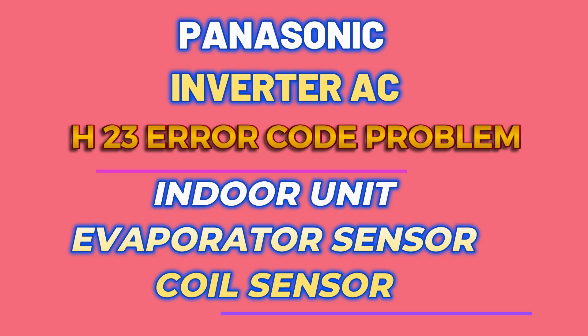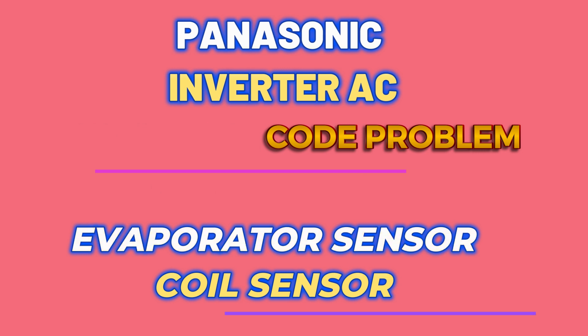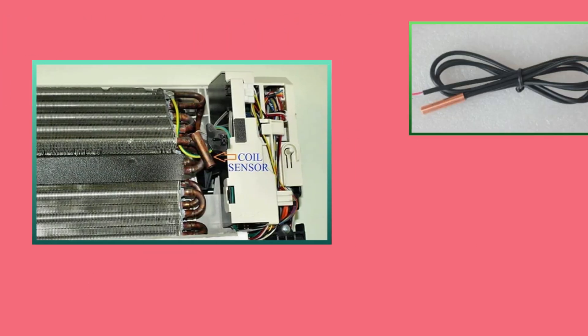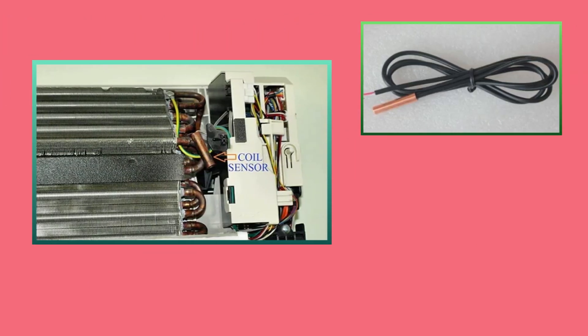If H23 is coming in a Panasonic AC, then it is the error of the evaporator sensor. In simple words, it can be called a coil sensor. This sensor is installed in the coil of the indoor unit.